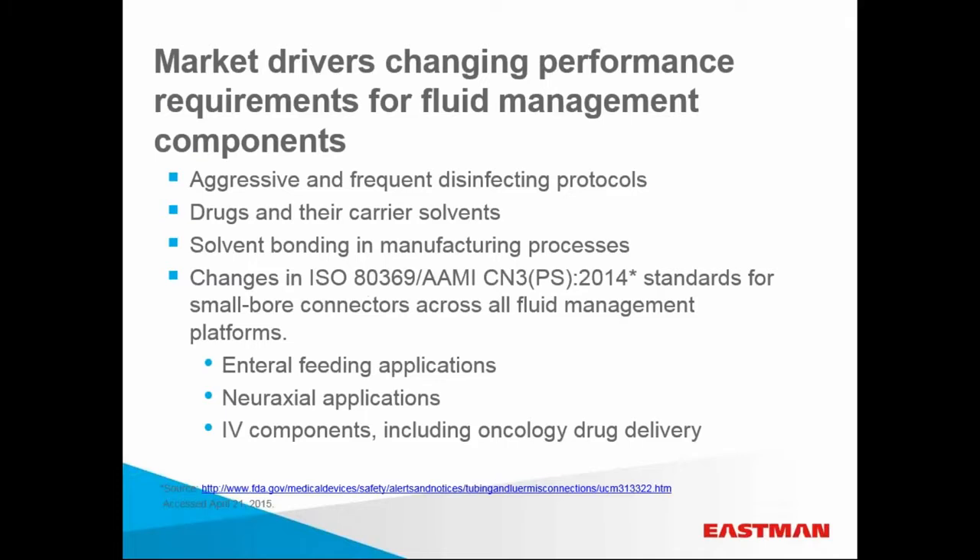In addition to disinfectants putting pressure on the outside of devices, and drugs and carrier solvents attacking from within, manufacturing processes including solvent bonding processes can erode the mechanical integrity of plastics. Meanwhile, international standards for small bore connectors are changing across all fluid management platforms. The ISO standard 80369 continues to move toward final approval and publishing, and will ultimately apply to all delivery platforms. Enteral feeding applications are published, and the FDA in the U.S. has adopted these standards. Neuraxial standards will be available soon, along with those for IV components.